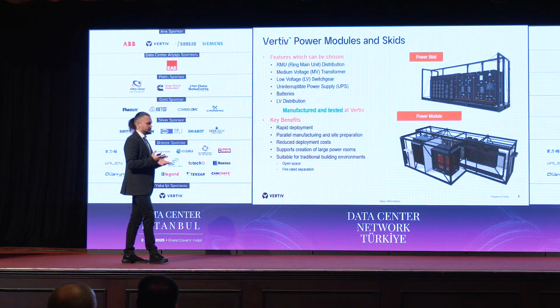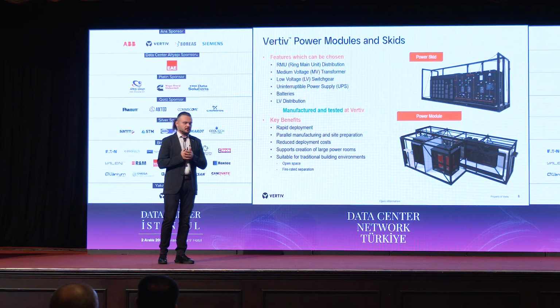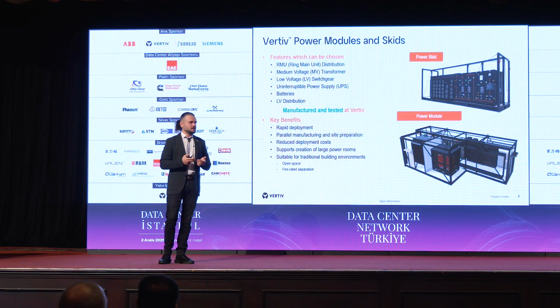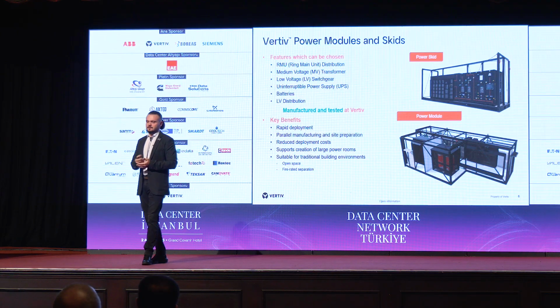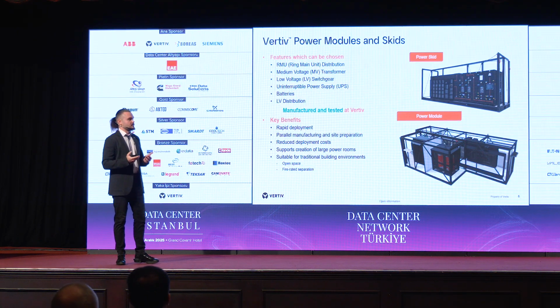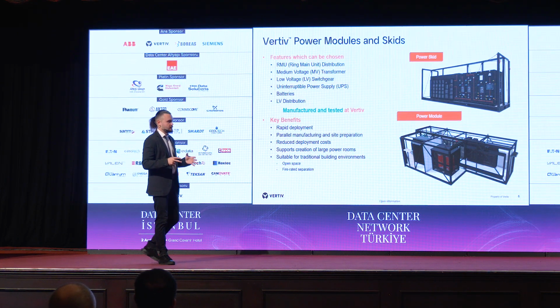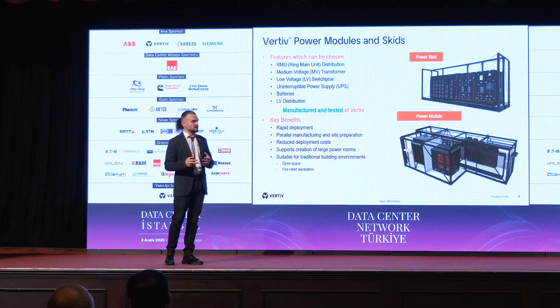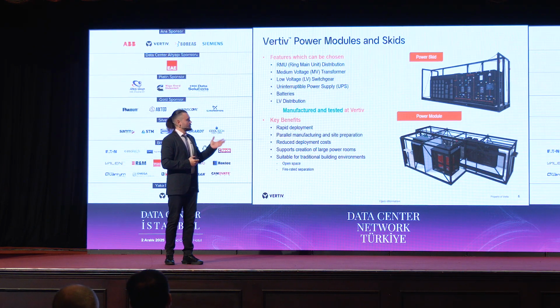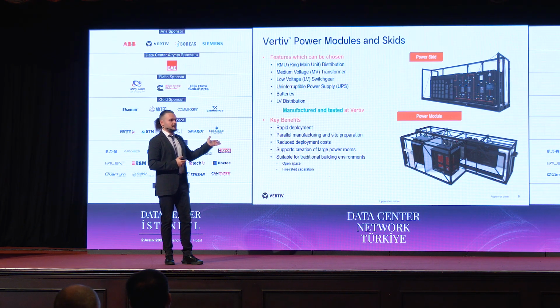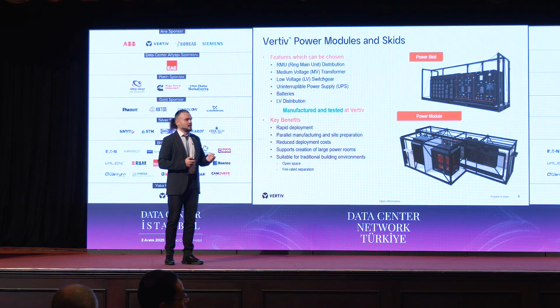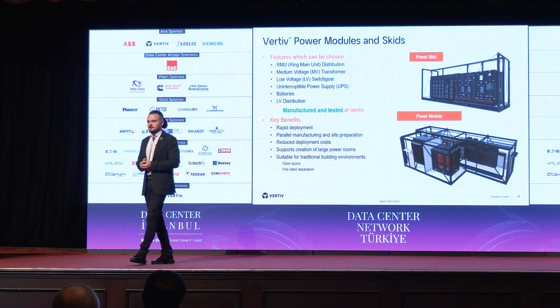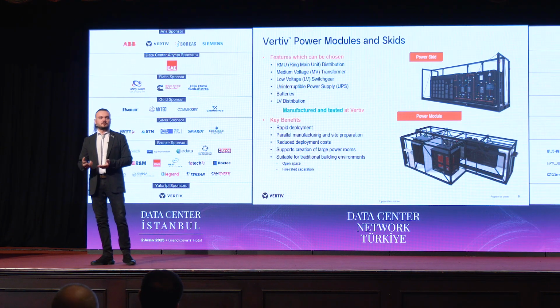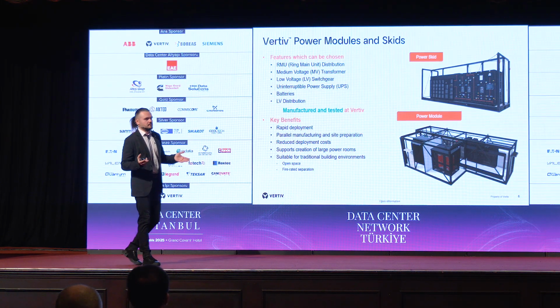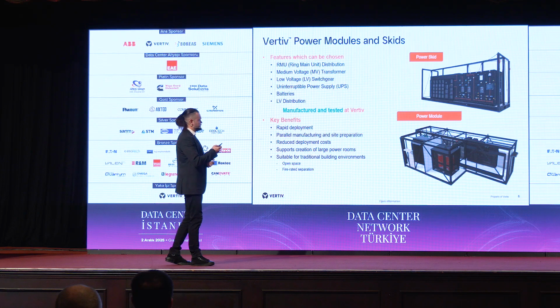It can be two types. On the screen you've seen the outside version, an outdoor enclosure. It has a lot of benefits, but if you're planning to build a bigger data hall or building, you can use the indoor version, a so-called skid. It will be just a platform with the switchgear and the UPS. The benefit of this solution is that it comes prefabricated and pre-tested, so plug and play, mostly.